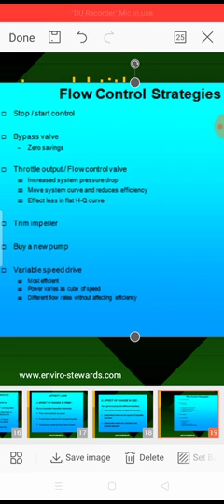Flow control strategies shown here: stop or start control, bypass valves, throttle output, flow control valve, which increases the system pressure drop, moves the system curve, and reduces efficiency, with less effect on a flat HQ curve; trim impeller, buy a new pump, and variable speed drive, which is the most efficient.